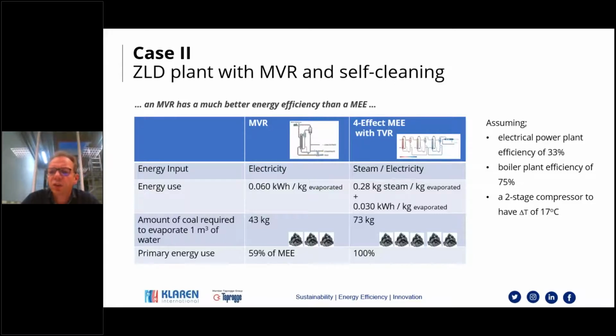And we need to take a starting point for the compressor that we use for the MVR. So in this case, we have taken a two-stage compressor having a delta T of 17 degrees. And then you can calculate that the electrical energy you use for the MVR is around 0.06 kilowatt hour per kg of evaporation. For a multi-effect evaporator plant, you have both steam consumption, but you also have the electricity consumption for all your circulation pumps and product pump. That would be the same for the MVR, but the circulation pumps, of course, are very important for an MEE plant, but also for the condenser and the cooling tower. So there you would see that we would need 0.28 kg steam per kg evaporated and around 0.03 kilowatt hour for the same amount. So you see that the electrical energy is already half of the MVR plant, so it's a substantial part.